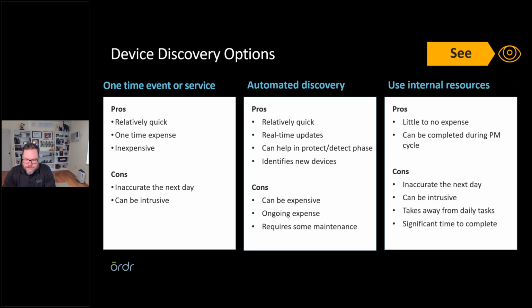Then the last one is to use what you have. Put together a process so that during your PM cycles, you gather this information. This is a good way to do it, but it takes time. Some devices you see once a year. Some devices nowadays you only see every 2 years, when you're looking at some of the new infusion pump stuff. So gathering it could take a lot of time, and it can be intrusive, taking that equipment down for a longer length of time. And it takes away from time that your technicians truly need to do their daily work.